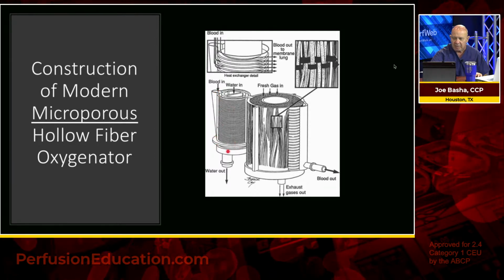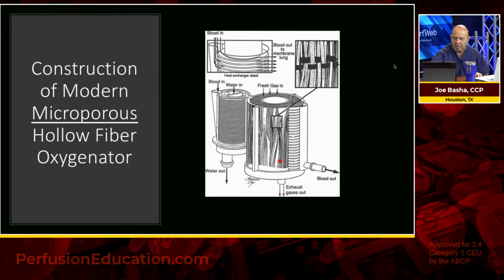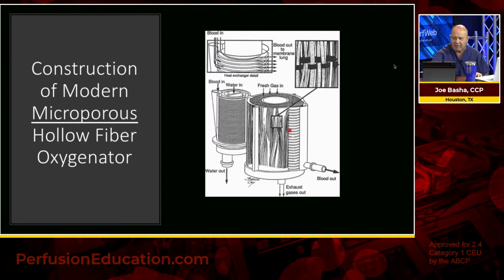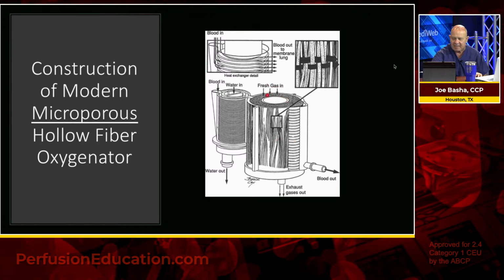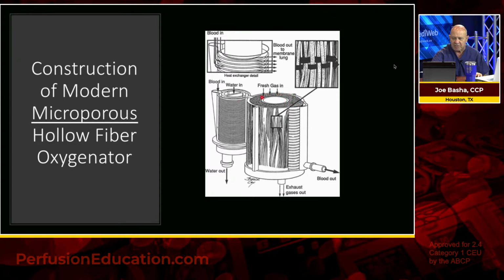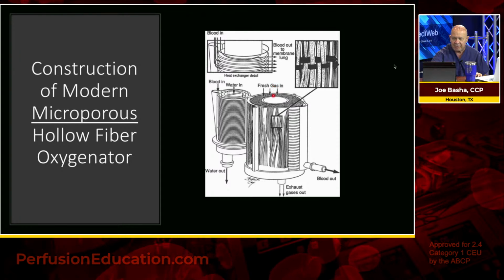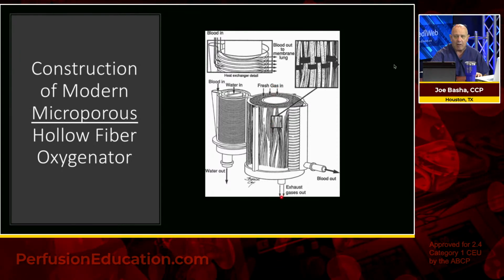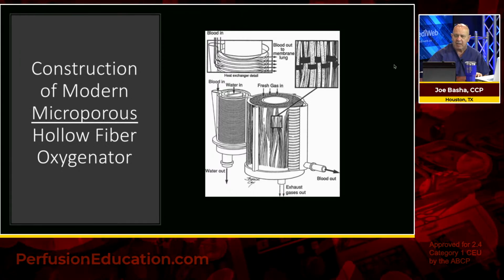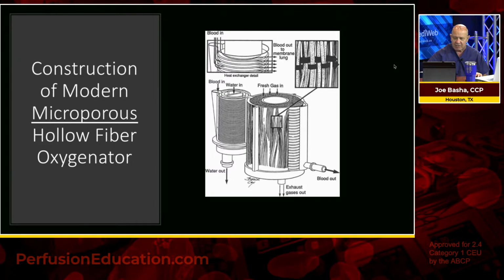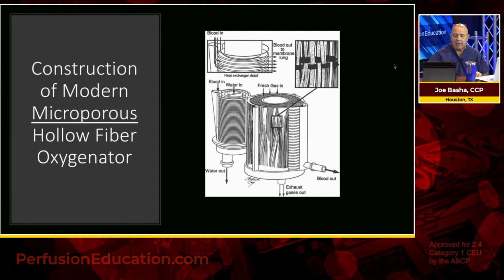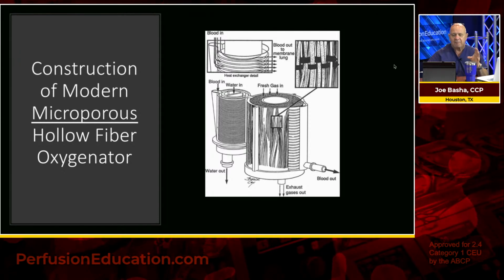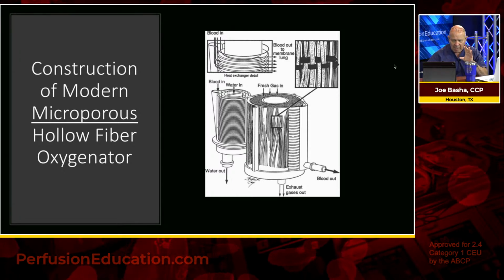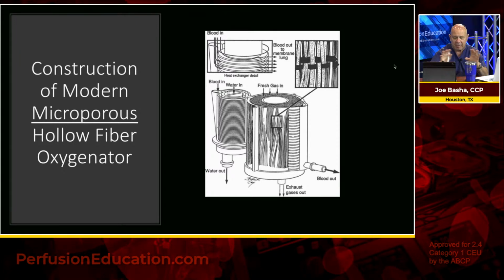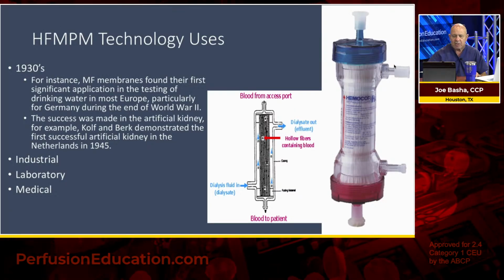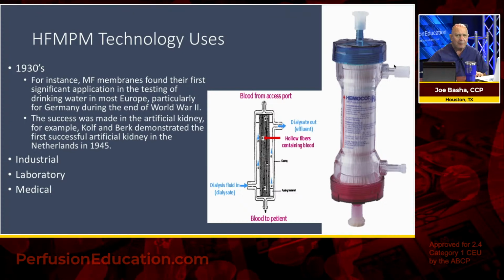You have your blood in, your blood crosses over into the oxygenator and comes out here, going again on the outside of the fibers. And you have your fresh gas coming in. This is a cross section, it's cut out, but of course it's potted and there's a cap on it. And you have your gas flow coming in and then your exhaust gas out down here. It's just one iteration of a membrane oxygenator, specifically a microporous hollow fiber oxygenator. It's not a true membrane, but we'll get into that a little bit as we go forward with this. So we're very used to hollow fiber technology.